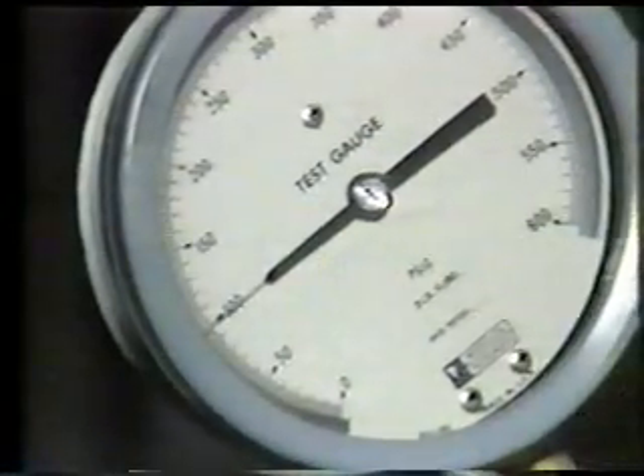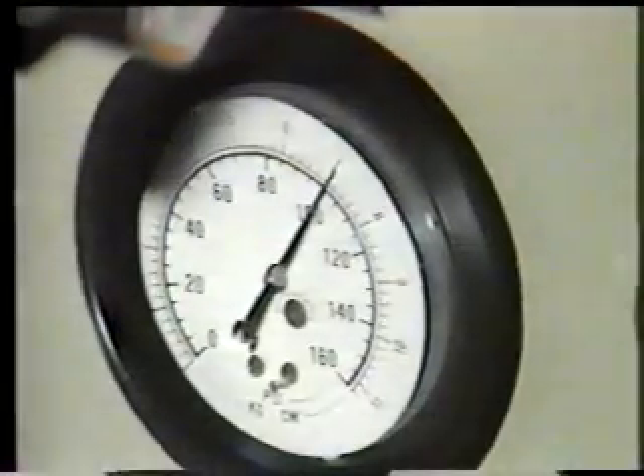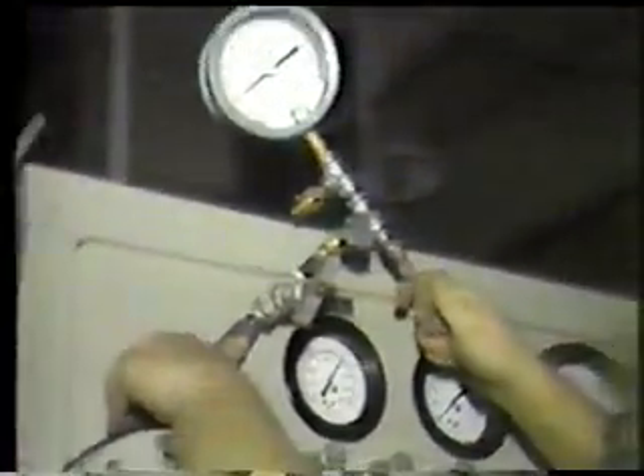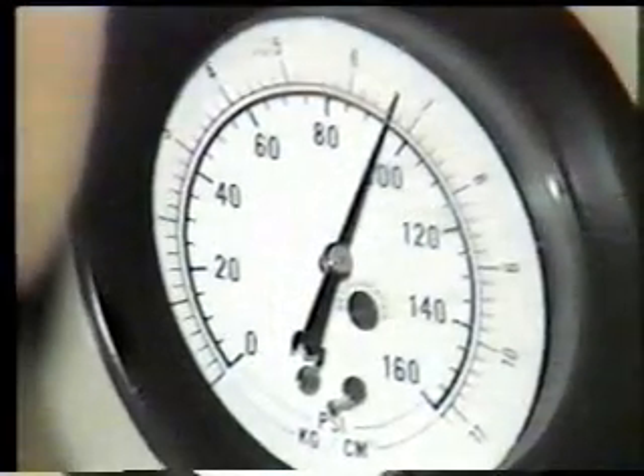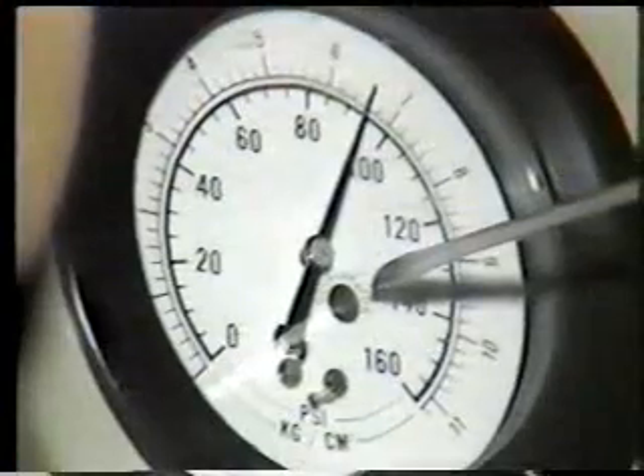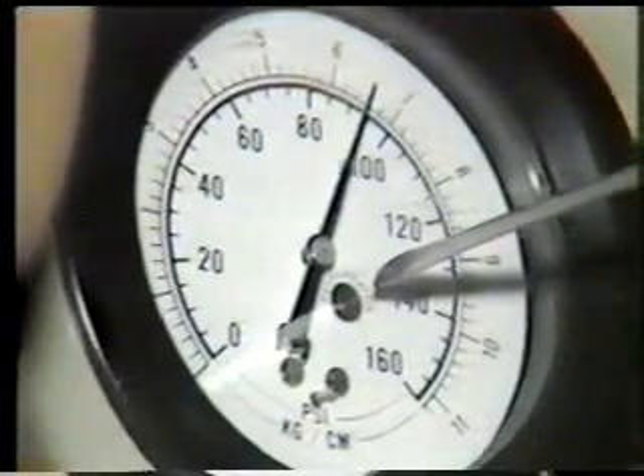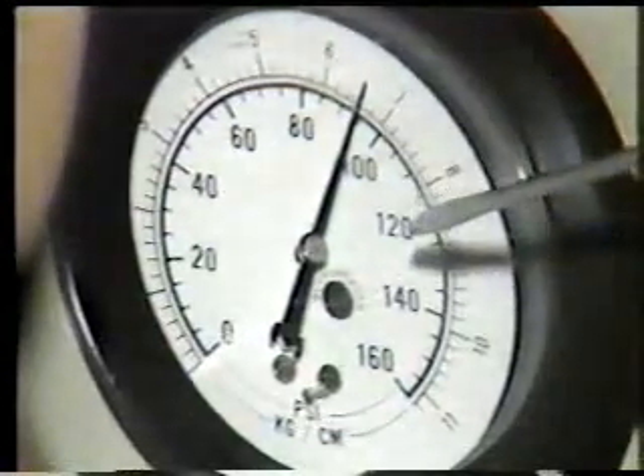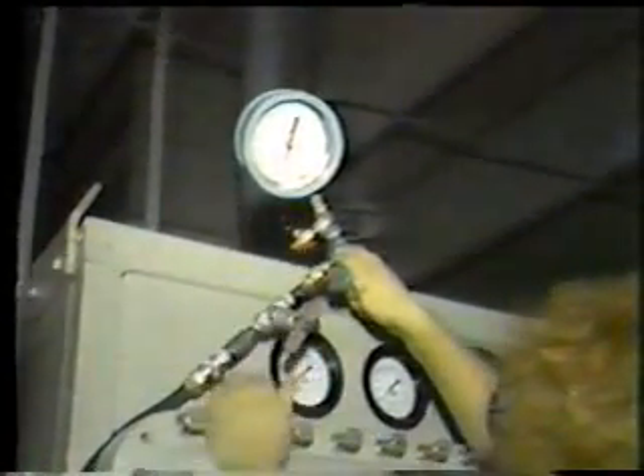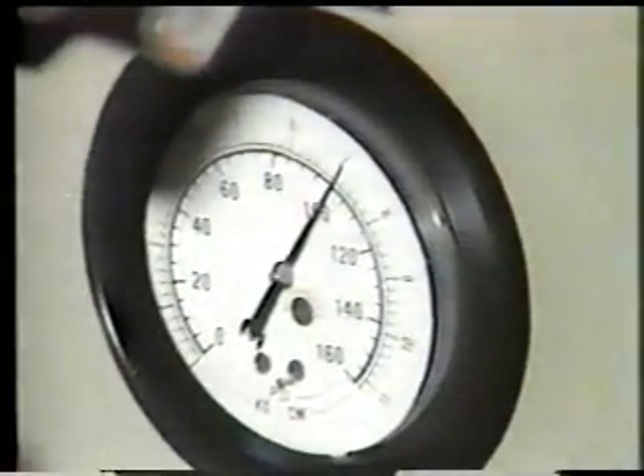Now, compare the pressure indication on the master test gauge to the gauge being calibrated. If the gauge requires adjustment, you would use the calibration screw on the gauge face. Further in the tape, we will go through this procedure in the lab. Once the gauge has been calibrated, slowly decrease, then increase the pressure to check gauge repeatability. When the calibration is complete, bleed the external pressure source to 0 and disconnect it.